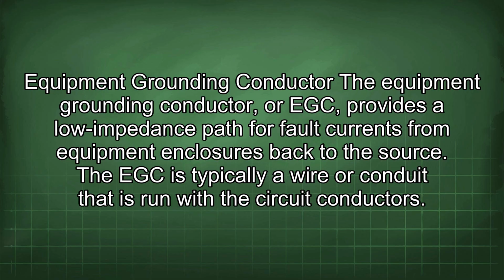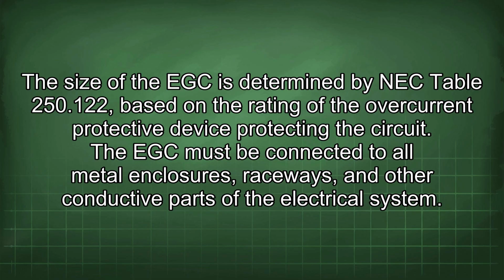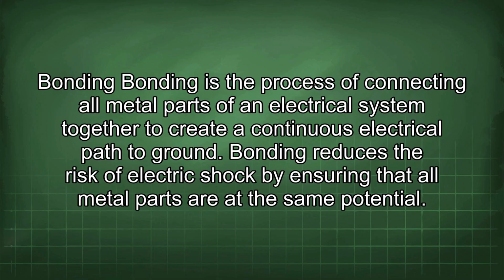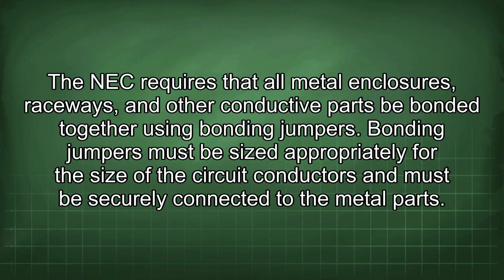Equipment grounding conductor. The equipment grounding conductor, or EGC, provides a low-impedance path for fault currents from equipment enclosures back to the source. The EGC is typically a wire or conduit that is run with the circuit conductors. The size of the EGC is determined by NEC Table 250.122, based on the rating of the overcurrent protective device protecting the circuit. The EGC must be connected to all metal enclosures, raceways, and other conductive parts of the electrical system. Bonding. Bonding is the process of connecting all metal parts of an electrical system together to create a continuous electrical path to ground. Bonding reduces the risk of electric shock by ensuring that all metal parts are at the same potential. The NEC requires that all metal enclosures, raceways, and other conductive parts be bonded together using bonding jumpers.